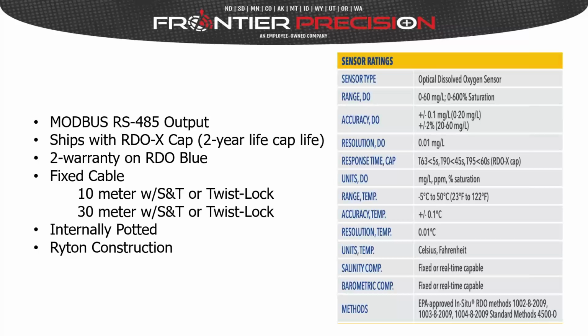So here are some of the specs for the RDO Blue. It's Modbus RS485 output. It ships with the RDO X cap that has a 2-year life on it. There's a 2-year warranty on the probe. All of the cables on the RDO Blue are fixed penetration style cables that are permanently attached to the sensor. However, on the back end, we have 2 types of cables available, stripped and tinned and twist lock, that you can get in 2 different lengths. Now, if you need to go greater than 30 meters, I'll show you in just a minute how you can do that. That's one of the main differences between the RDO Blue and the RDO Pro X. The RDO Pro X had a quick connect directly on the sensor as well as on the end of the cable, whereas it's potted on this one, which makes it quite a bit less expensive than its predecessors.